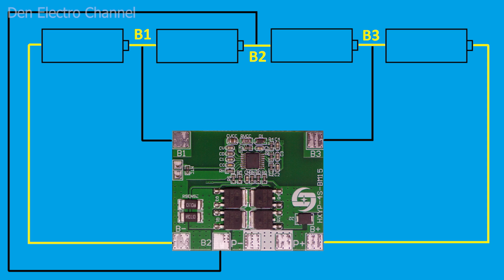The wires marked in yellow should be thick, since all the huge current will flow through them. Black wires are signal wires. Using them, the BMS measures the voltage on each battery. There is no large current here, so thin wires can be used. The P plus and P minus terminals connect charging and load.